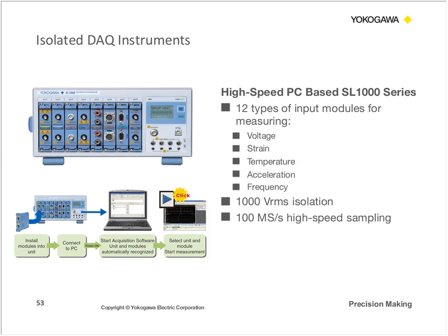And lastly, we also have a PC-based data acquisition device. So this is the SL1000 series. This fits perfectly well into automated test systems, fully compatible with LabVIEW and MATLAB. So this is very good if you're running an automated system and you don't want to run the risk of harming the user, or maybe you have a test cell environment where the user cannot easily access the instrument. So this is another one of the solutions that we have for measuring high voltages at high speeds without running the risk of being exposed to these high voltages.